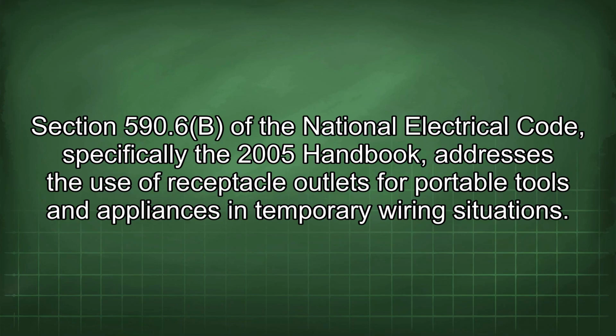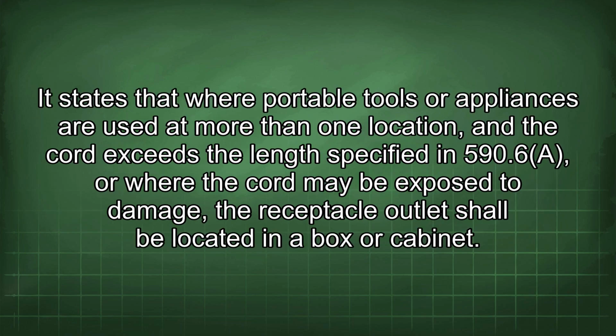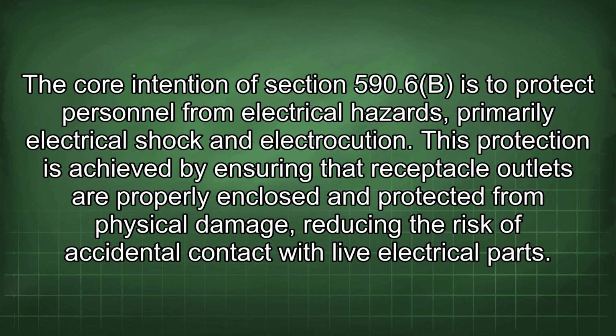Section 590.6b of the National Electrical Code, specifically the 2005 Handbook, addresses the use of receptacle outlets for portable tools and appliances in temporary wiring situations. It states that where portable tools or appliances are used at more than one location, and the cord exceeds the length specified in 590.6a, or where the cord may be exposed to damage, the receptacle outlet shall be located in a box or cabinet. The core intention of Section 590.6b is to protect personnel from electrical hazards, primarily electrical shock and electrocution. This protection is achieved by ensuring that receptacle outlets are properly enclosed and protected from physical damage, reducing the risk of accidental contact with live electrical parts.